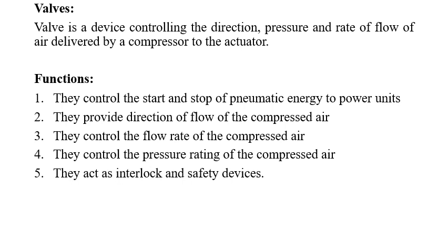They control the pressure rating of the compressed air. The pressure rating is important to push or to lift the load using a pneumatic system. Depending on how much load you need to lift, and depending on the area of the piston, you need to decide what pressure you require. If the pressure drops below that, the required work will not take place. So to lift the load, the pressure is very important. We need to maintain the proper pressure. If we increase the pressure, it will be hazardous to the system. If we decrease the pressure, the required work will not be completed.